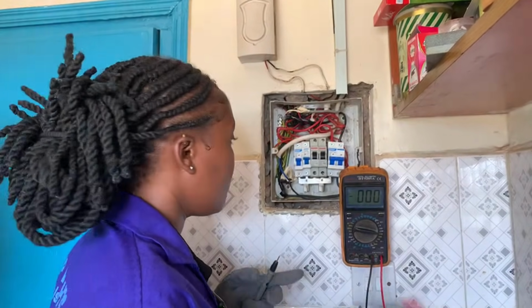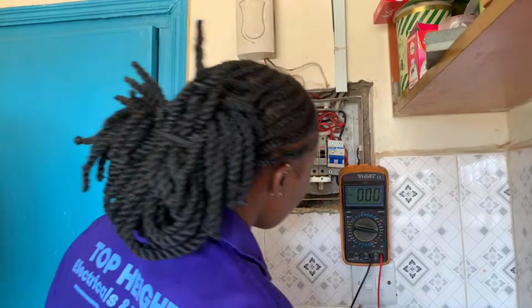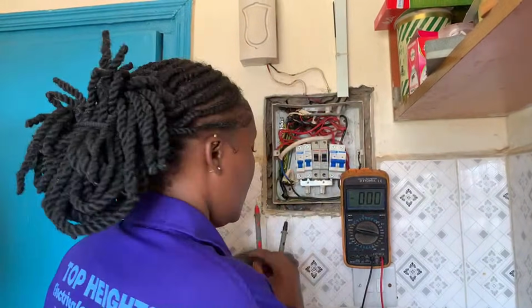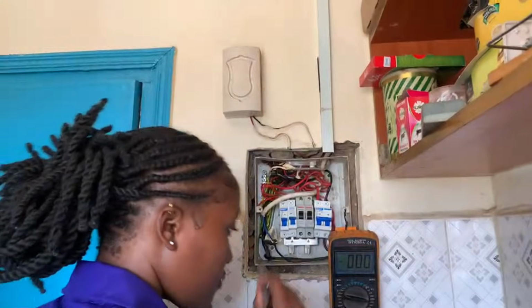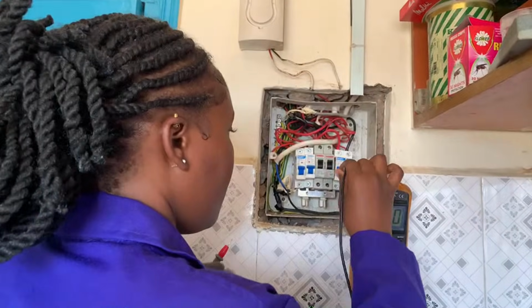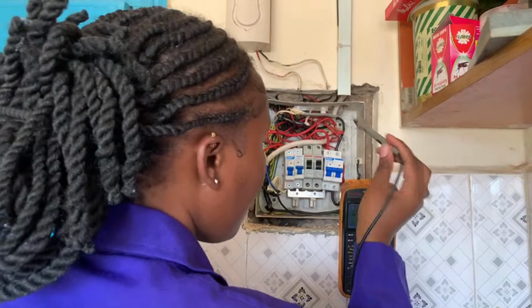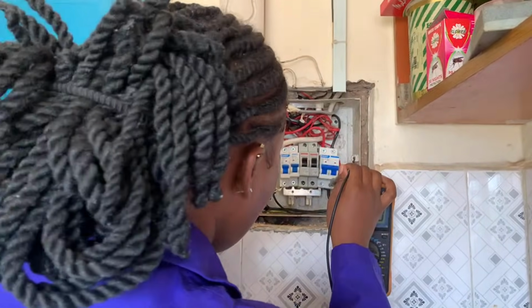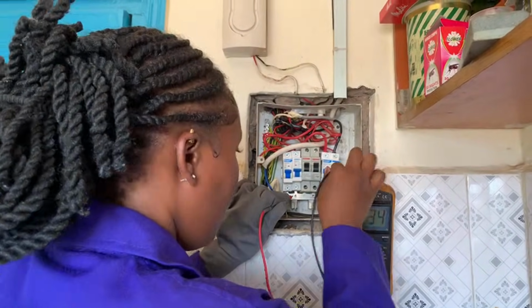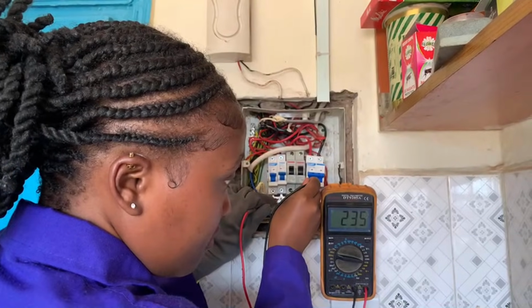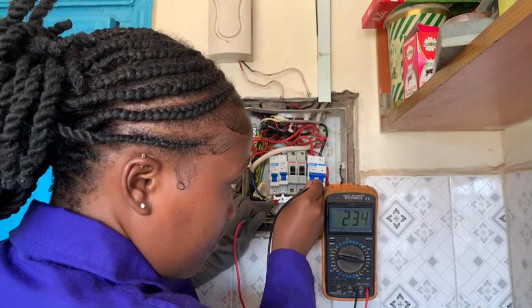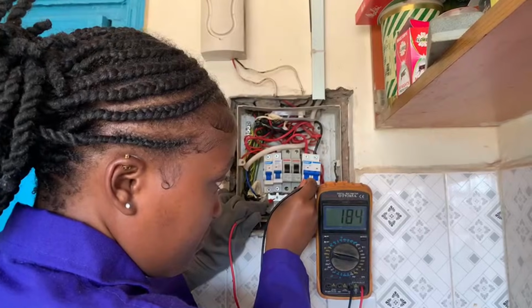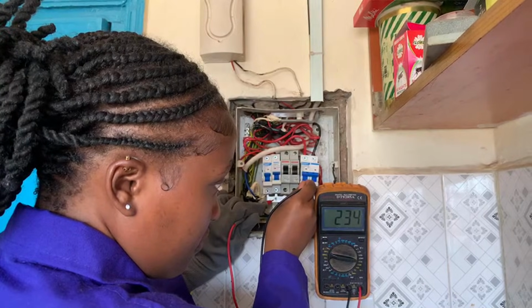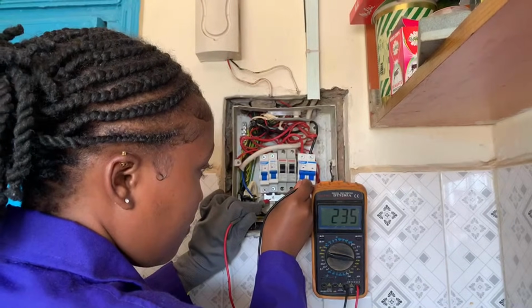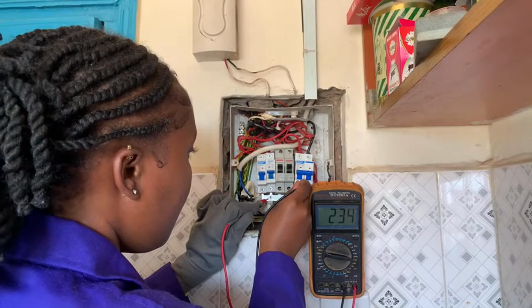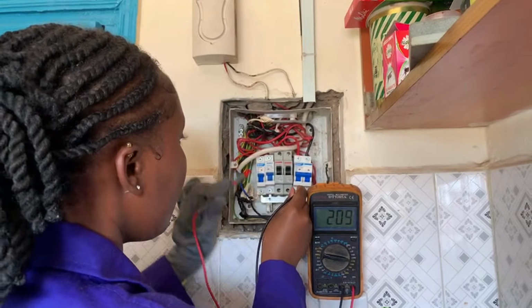Now we test on the neutral, right? The neutral and the bar. The neutral on the output, outputs. Let us see. Good job. Now we want to test on the output so that we can be sure that all the MCBs are giving an output. So the neutral should remain there, and then the red probe, test it on the output above each MCB.